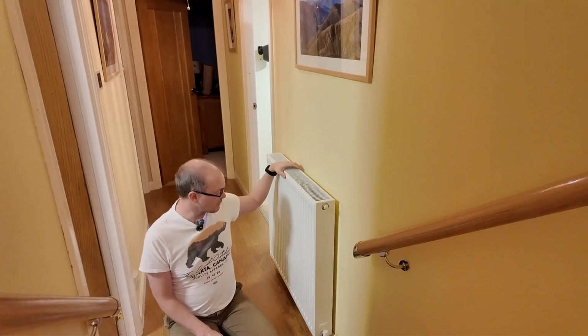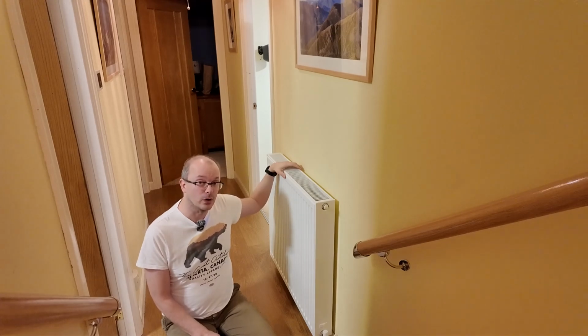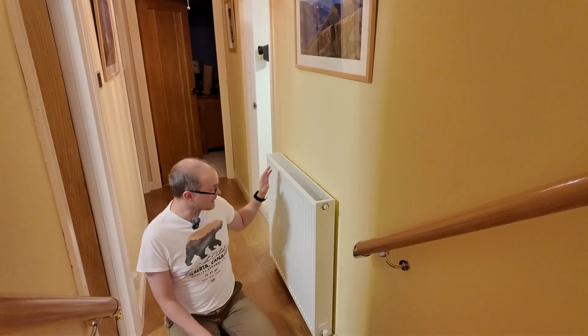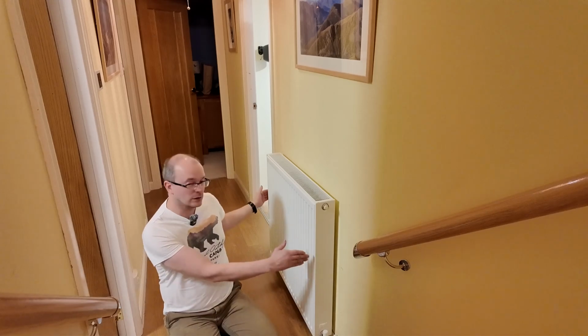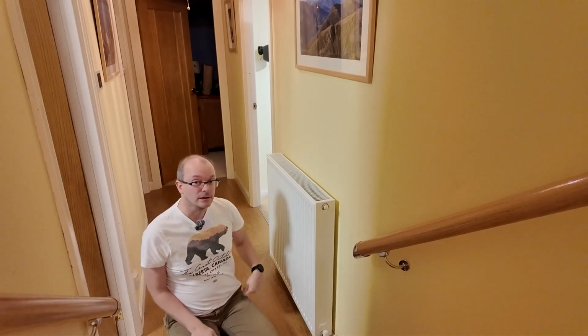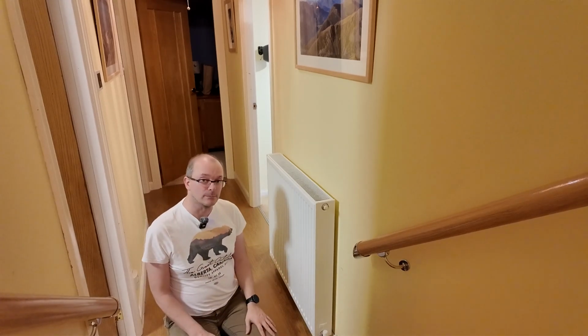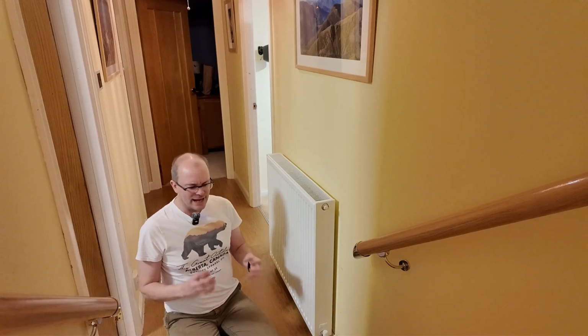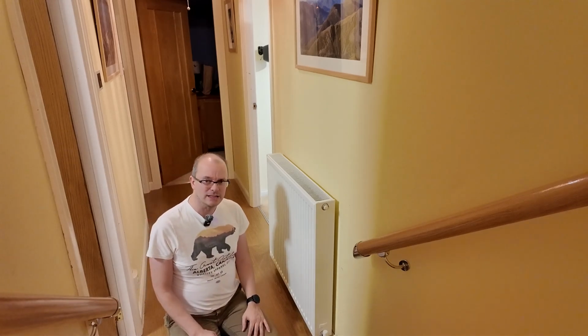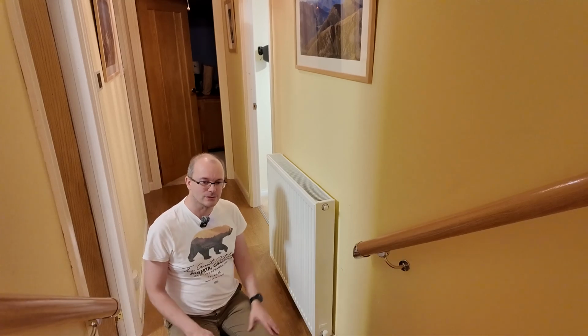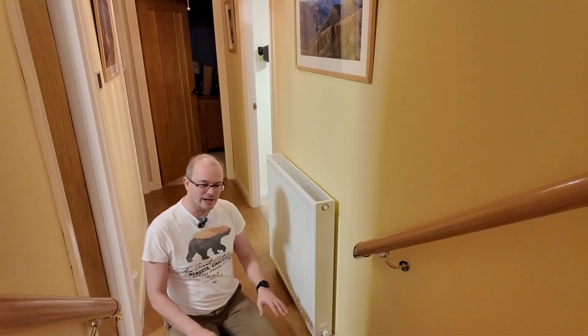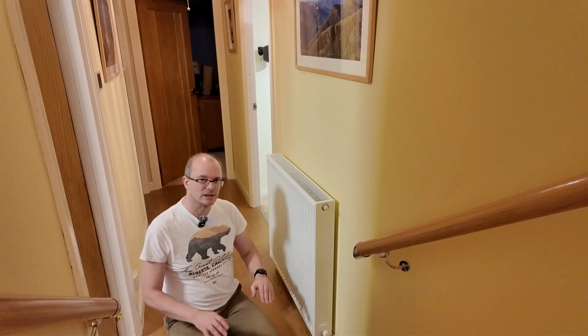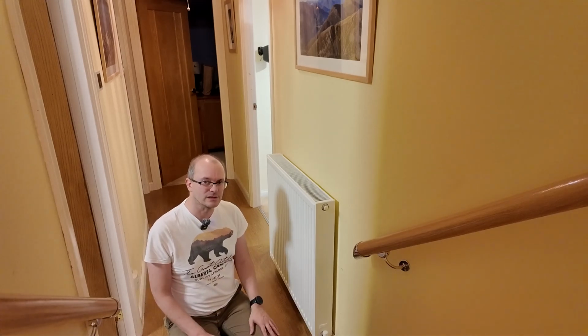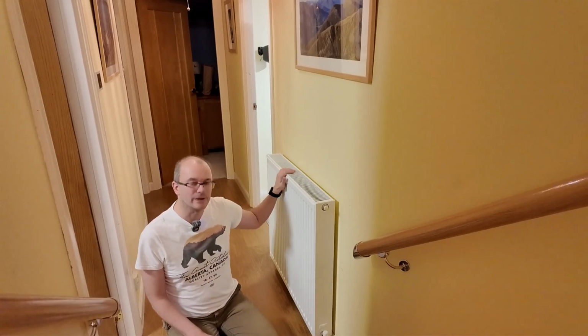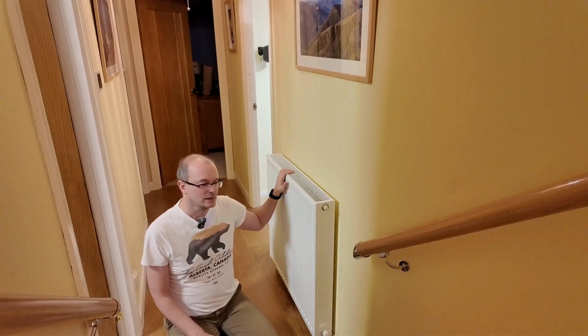These radiators, they're about 3 times the rated output of my original radiators, and in physical terms, they're only a little bit longer and a little bit higher and twice as thick. And they don't really take up much space at all. And yet conventional wisdom is that you need to have underfloor heating in order to have a radiator system which is flowing at no higher than 30 degrees Celsius. I've now proven that this is incorrect.